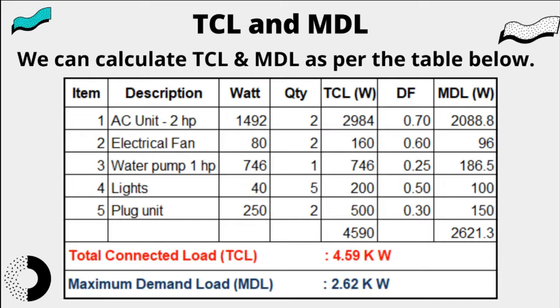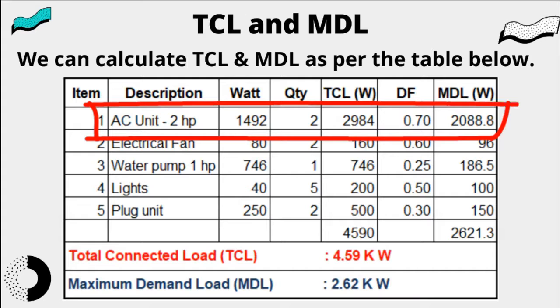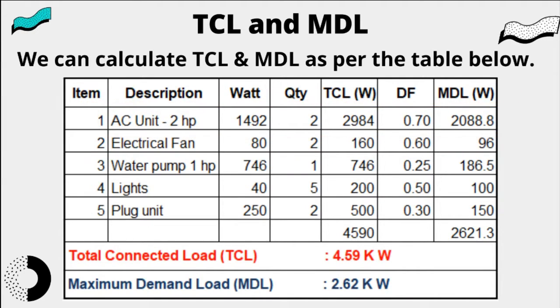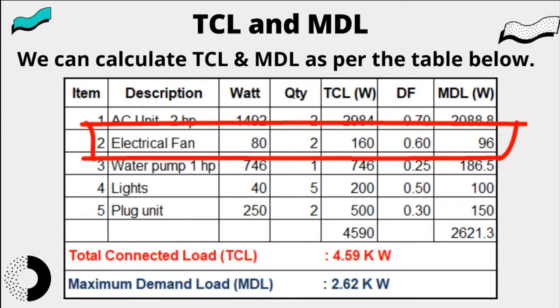Let us analyze the table. The total load of the two AC units is 2984 watts and the MDL is 2088 watts as the DF is 0.70. The TCL of the two fans is 160 watts and the MDL is 96 watts when the DF is 0.60.